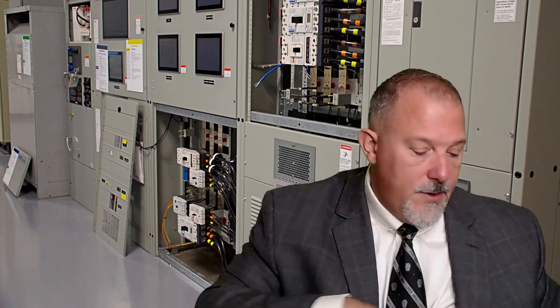And look at the latest one, which I think is a significant one, in Article 408. Let's take a look. 408. I could never find this one. 408.6. Remember, 408 is titled Switchboards, Switchgear, and Panelboards. 408.6 is Short Circuit Current Rating. Switchboards, switchgear, and panelboards shall have a short circuit current rating not less than the available fault current. In other than one- and two-family dwelling units, the available fault current and the date the calculation was performed shall be field marked on the enclosure at the point of supply. The marking shall comply with 110.21(B)(3).